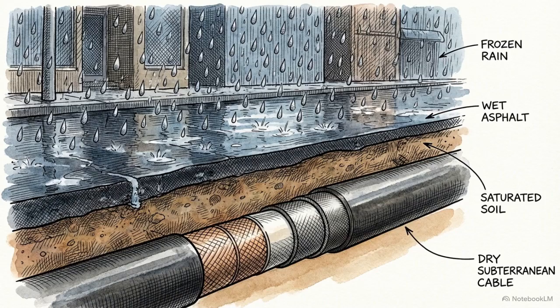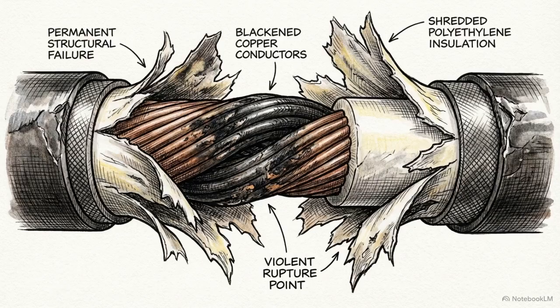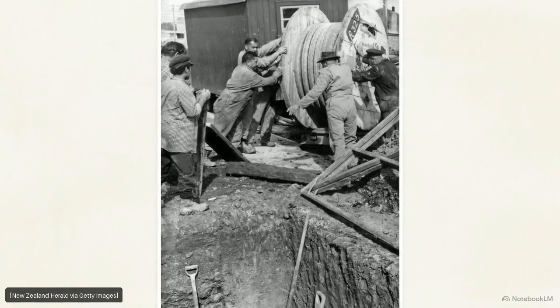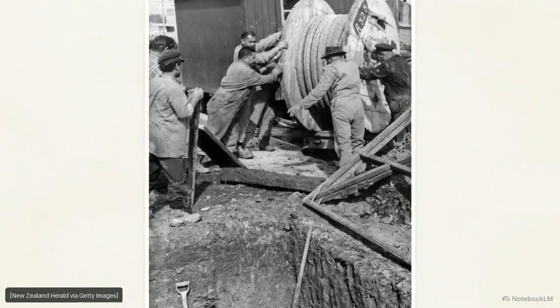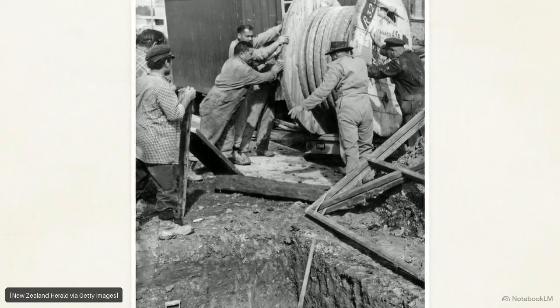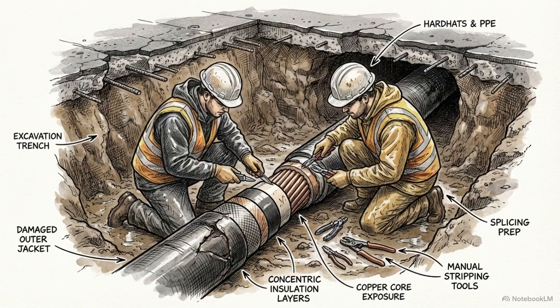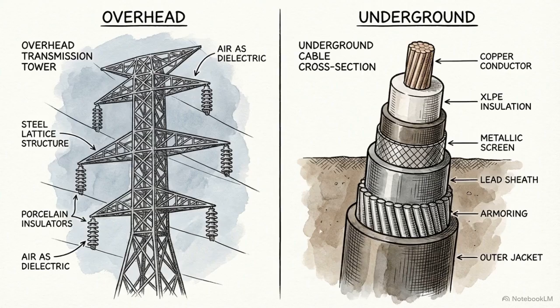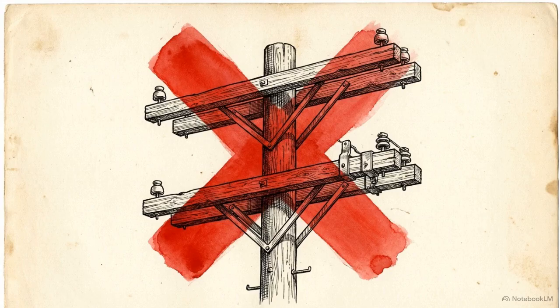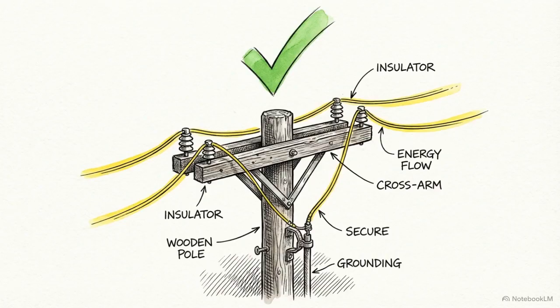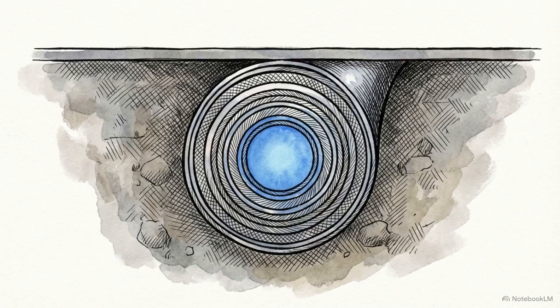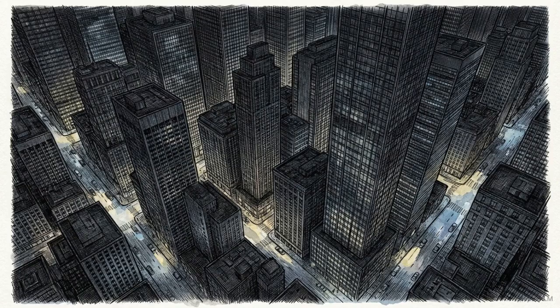Underground cables are largely immune to weather. But when they do fail, often from degraded insulation or an accidental backhoe dig-in, the damage is permanent. There is no automatic reset. Crews have to use specialized equipment to pinpoint the exact location of the hidden fault, excavate the street, and painstakingly splice those complex insulating layers back together. This creates a stark operational trade-off. Overhead lines fail frequently, but can clear themselves instantly. Underground lines fail rarely, but when they do, a quick flicker becomes a multi-day blackout.